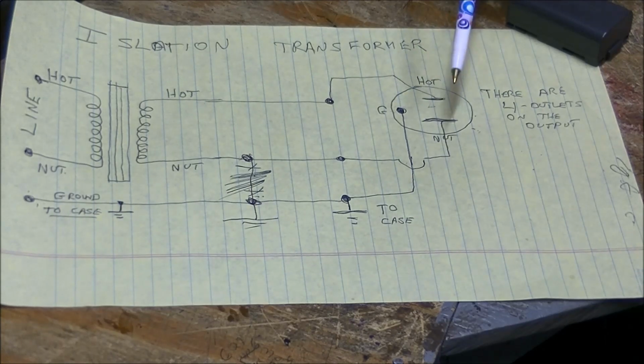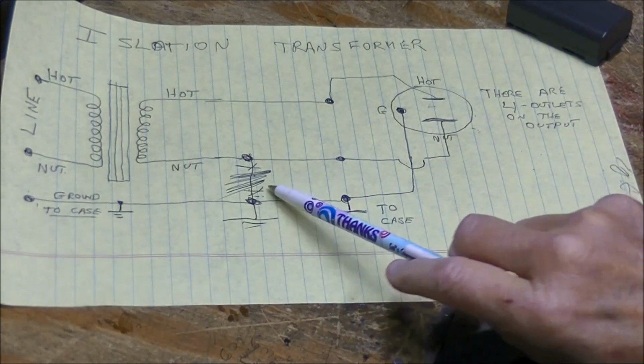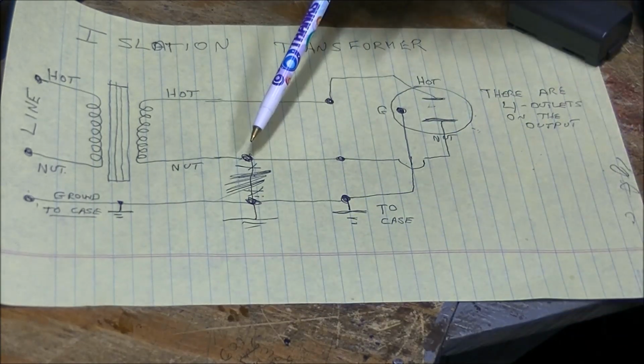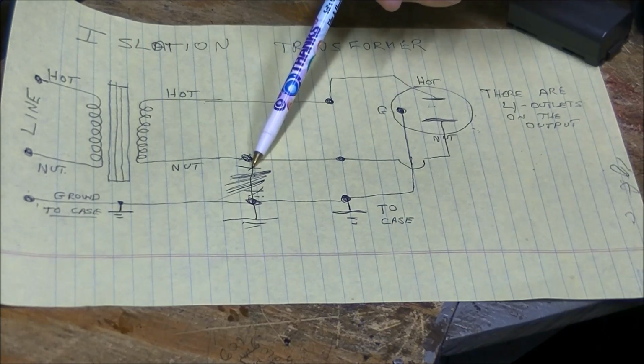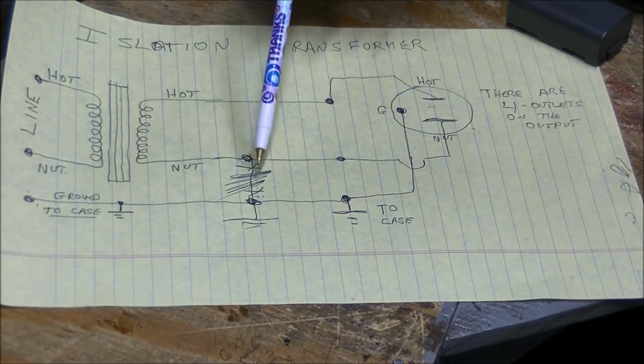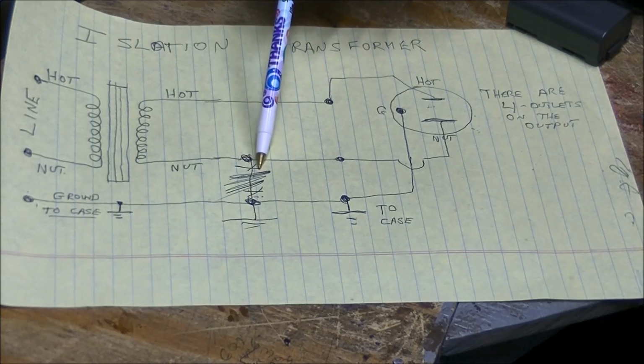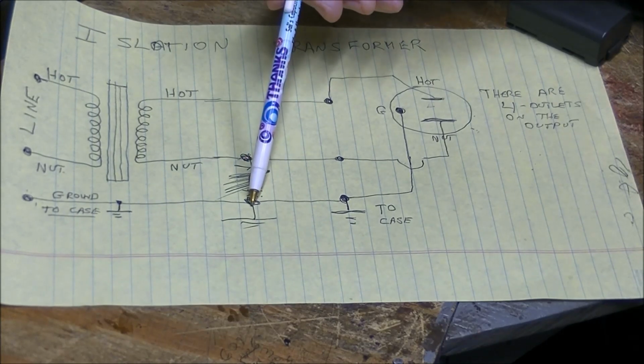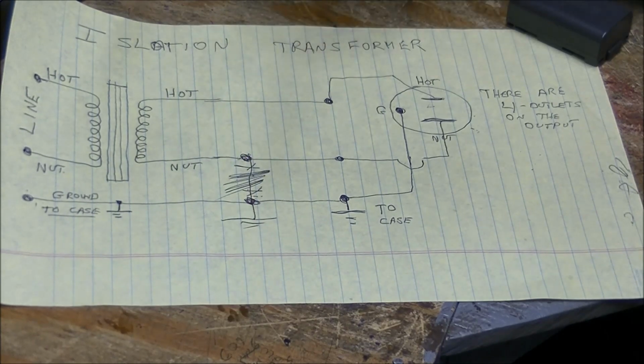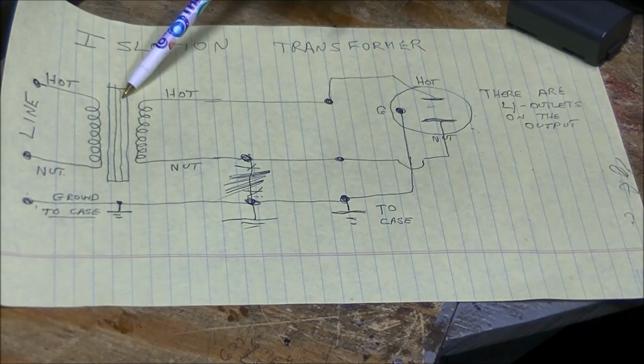So I removed the bonded neutral, and that's all you need to do. So if you get a transformer such as this, with the neutral bonded, and you want to use it as an isolation transformer, just unbond the neutral from the ground and the green wire, and you'll have an isolation transformer.